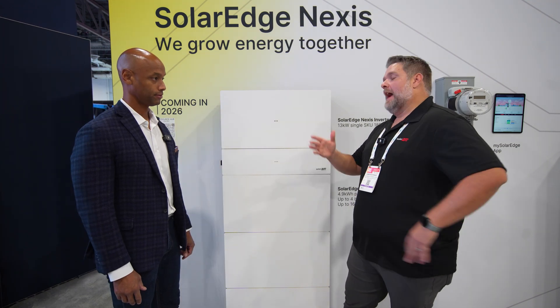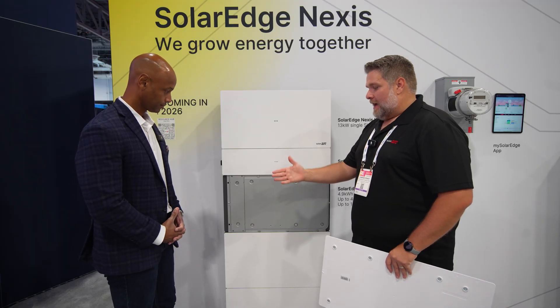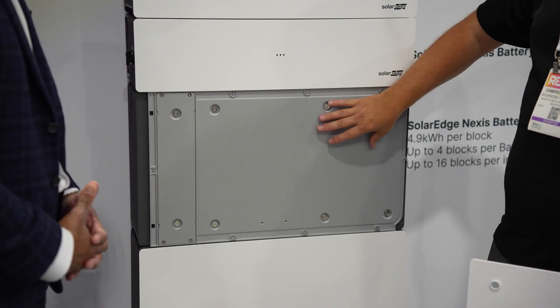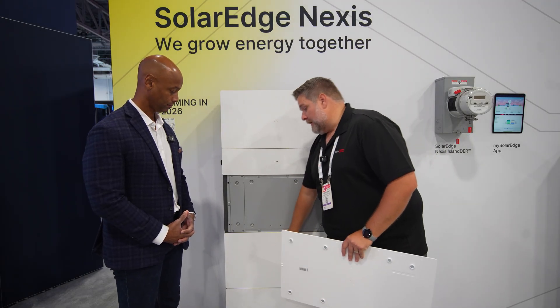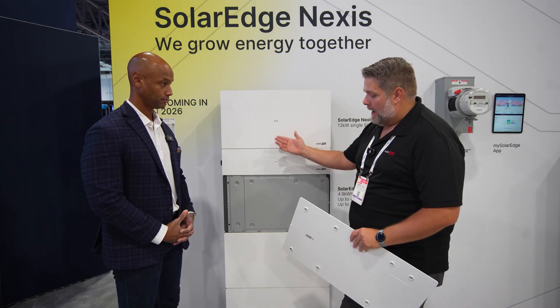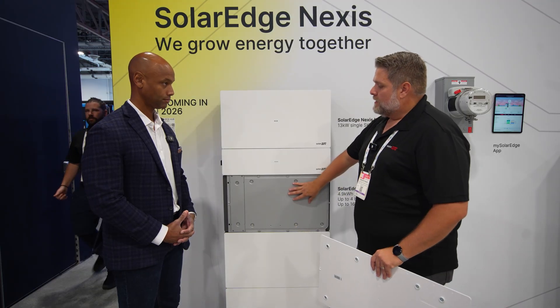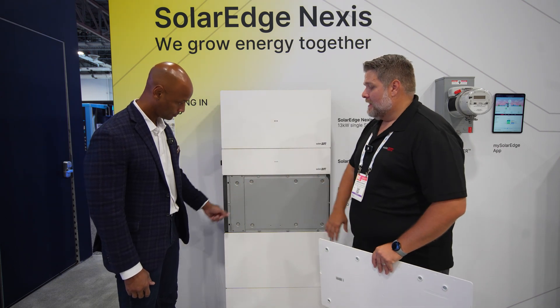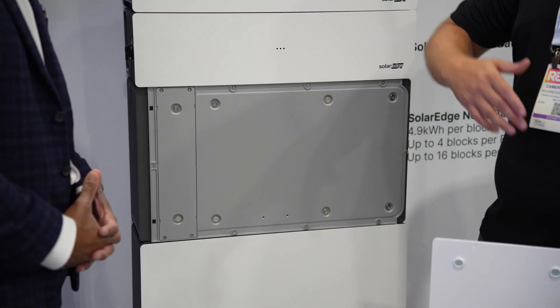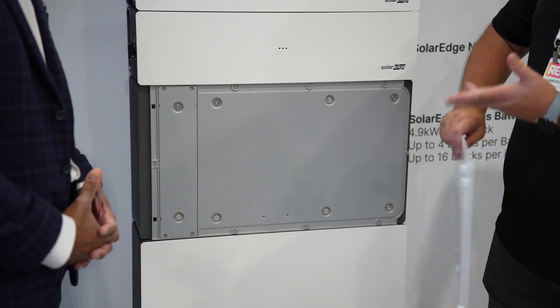Have we moved to LFP chemistry now with the new Nexis system? Yes — the market has spoken, we have listened, everything is LFP chemistry now. As far as serviceability goes, we thought about the flaw of modular batteries: what if a middle battery stops working? The other batteries continue to operate, but you don't want to unstack the entire stack to reach it. So we made a service compartment — you can take it off, replace the BMS, and put it back in without removing the battery from the stack or shipping chemistry across the US. You can service this battery with four screws.